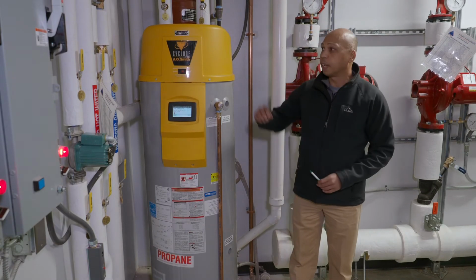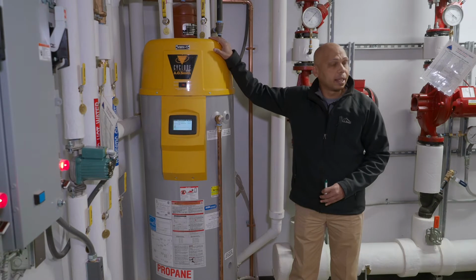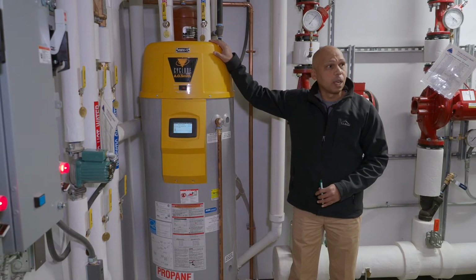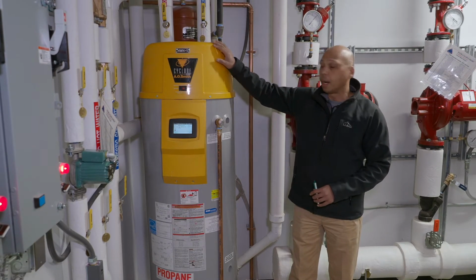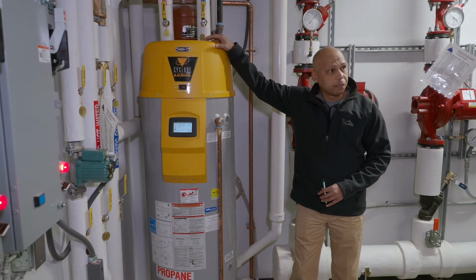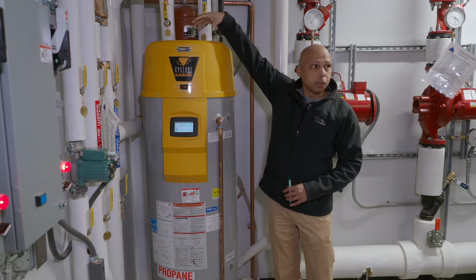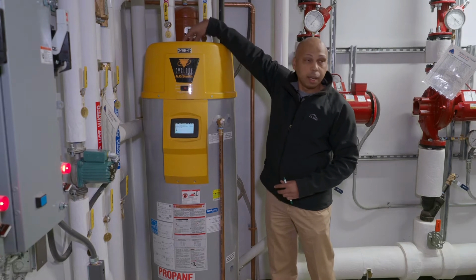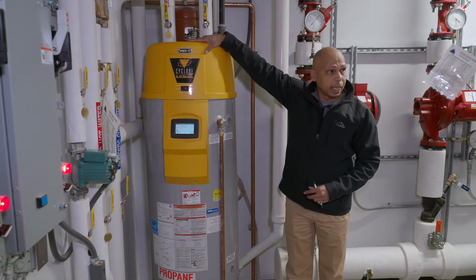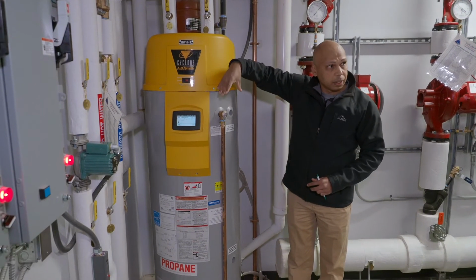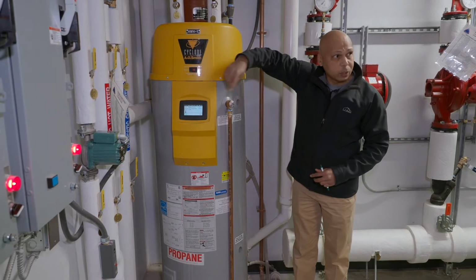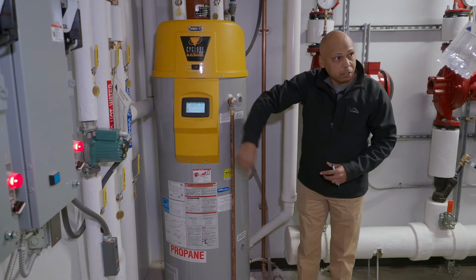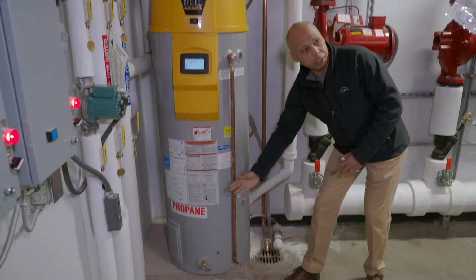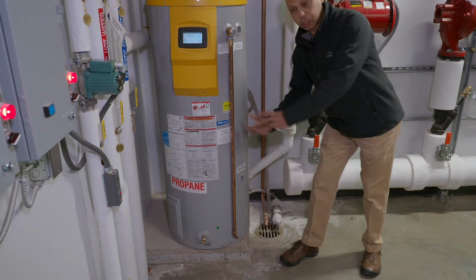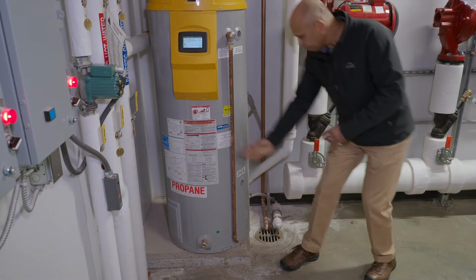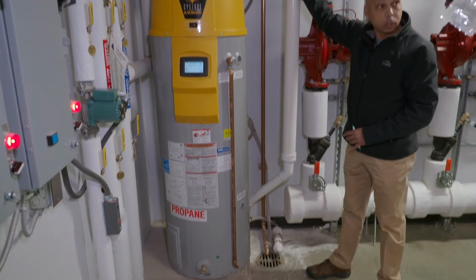Here I have an A.O. Smith Cyclone high efficiency water heater. VTX 100 is the model. It's over 95% thermal efficient. It's a top-down burner. So the burner's on the top here behind this yellow casing, and it's pushing all those exhaust gases through a helical heat exchanger, spiraling down. Cold water is passing through the heat exchanger, scrubbing off all that heat, and going up into the exhaust.